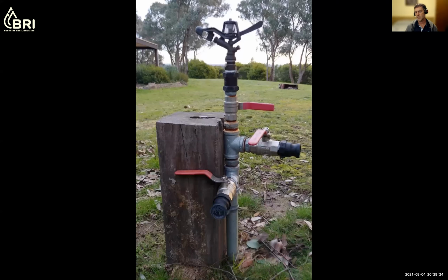I'd say copper is really reliable, and I'd put copper standpipes coming out of the ground with no problem. I've seen really reliable systems with copper exposed to direct flame contact, and it's fine. I'd avoid using timber, even hardwood, as the backing post, like in this example, especially not treated pine, and preferably not hardwood either. A steel support backing pipe for your standpipes would be more appropriate.